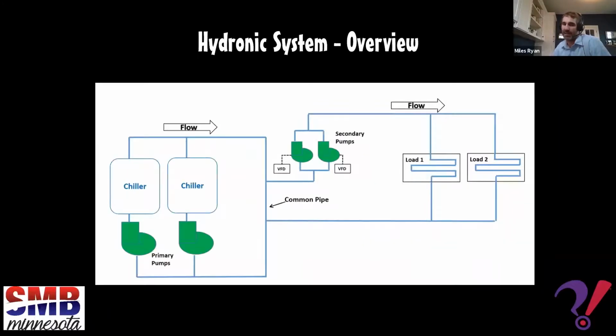A primary secondary system is a little bit different, but these are very common. They've been installed for years in many applications. They're still being designed and installed. I'm not going to go into all the nuances of a primary secondary system, but I will say there are primary pumps associated with primary equipment, chillers in this case, and primary pumps typically operate at a constant speed. If this left-hand chiller turns on, its associated primary pump turns on, and it's pushing flow at a design flow. It's not modulating the flow through that chiller.